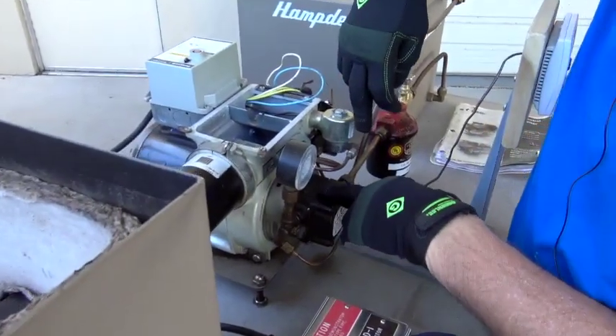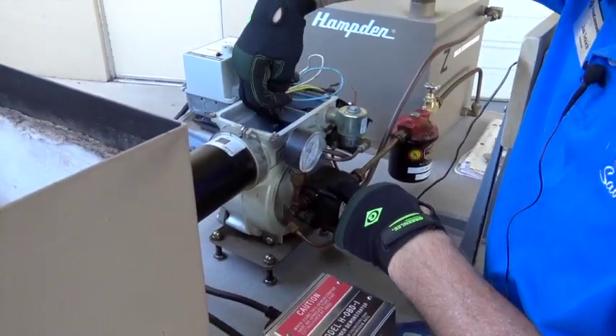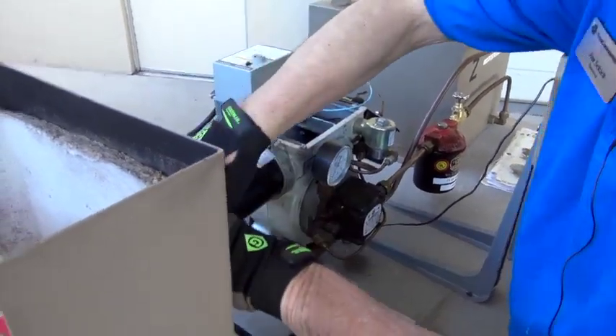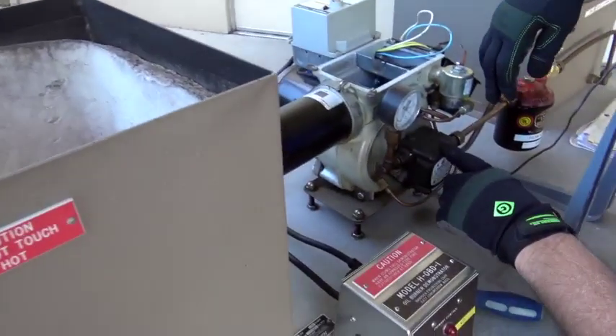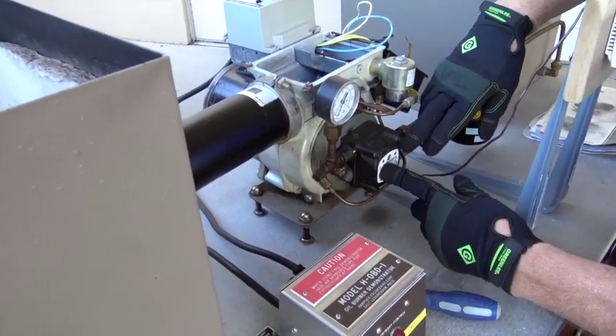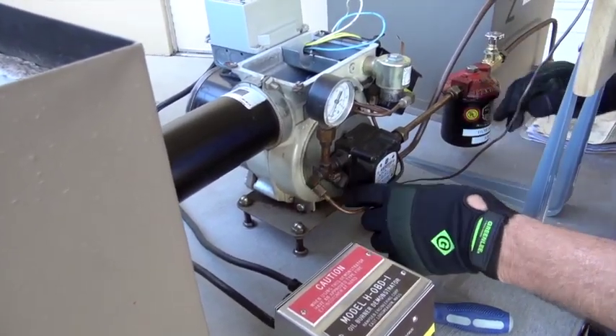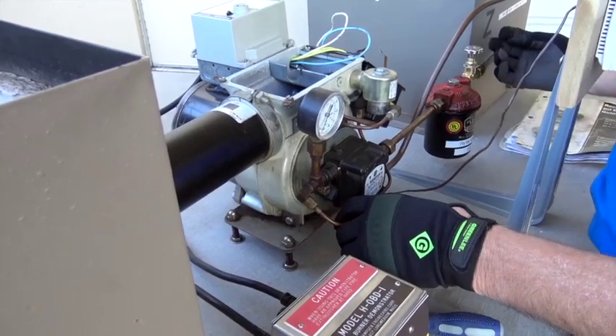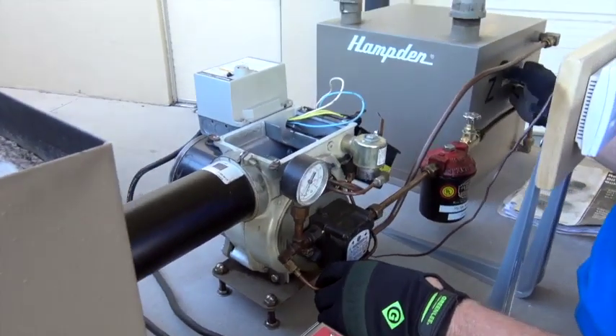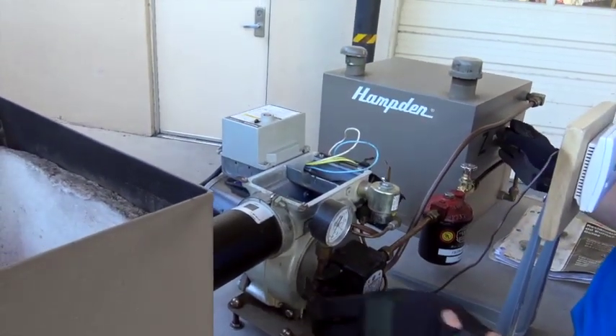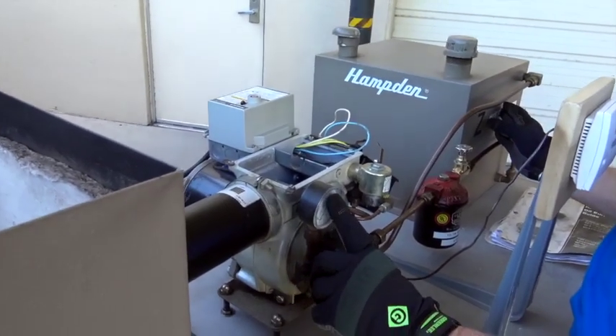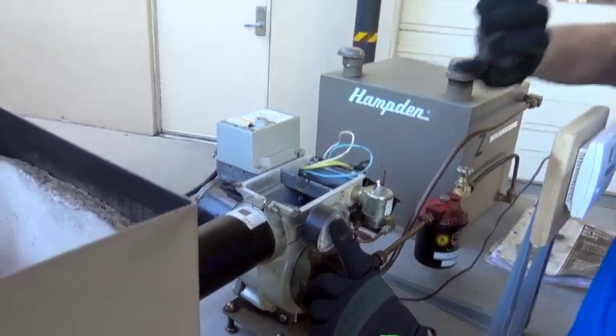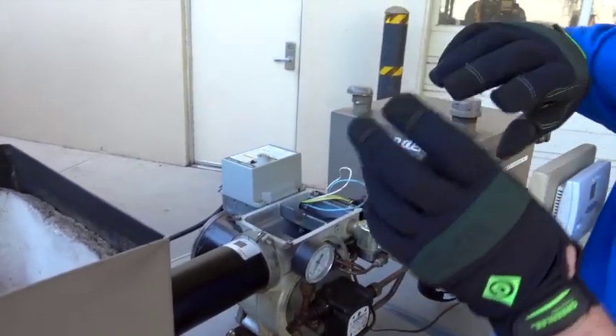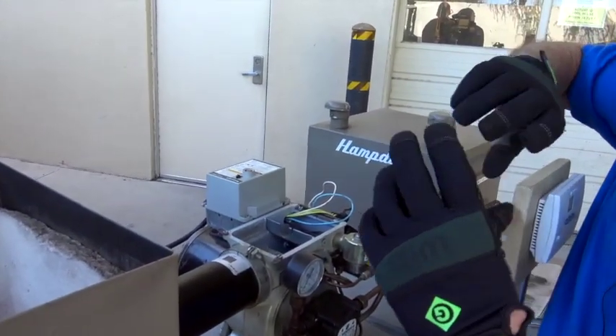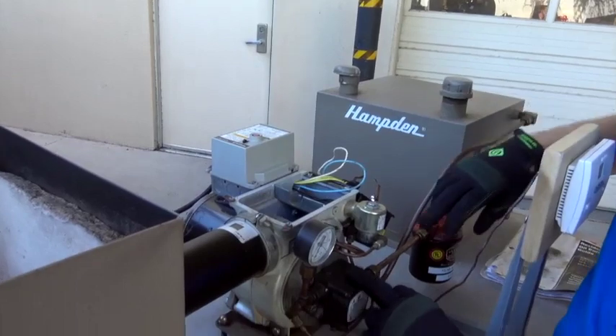As you can see, this motor pump assembly is going to provide combustion air through our combustion air tube, so we can combust. And also we have a pump assembly on it that's going to pump the fuel. We have to bring this pressure up from this fuel because we're sitting here at regular atmospheric pressure. So we're going to have to increase this pressure to about 100 psig. And remember, you got to go through that little nozzle. So we're going to take that and atomize that fuel. And so we're going to pump it.